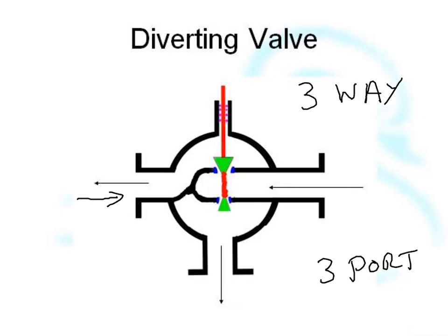That's a real problem. One of the important things to notice about a three-way valve is that the flow going in is always maintained. So there's always the same flow going in because it's either going at the top or it's going at the bottom. So you always have the same flow in, but if you pipe this up the wrong way, you're able to shut the flow off, and that can be a real danger.